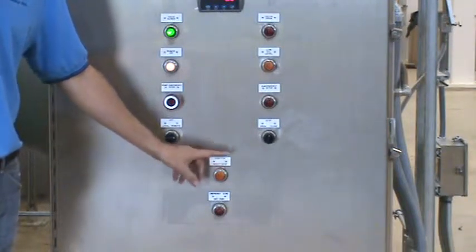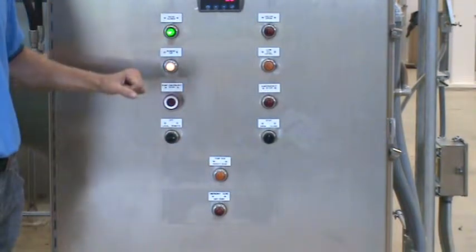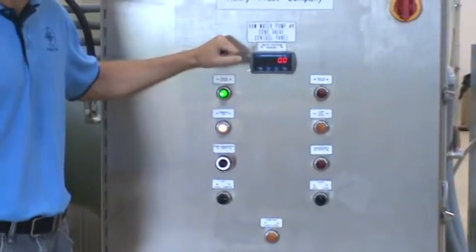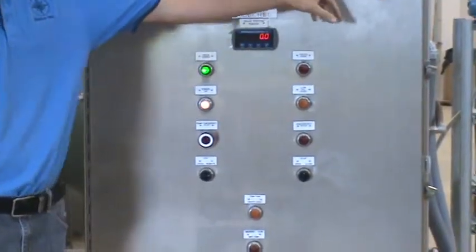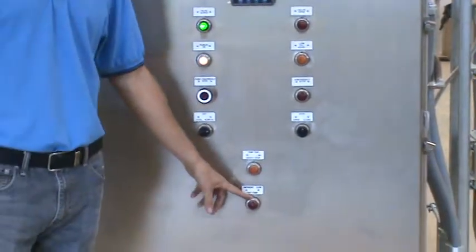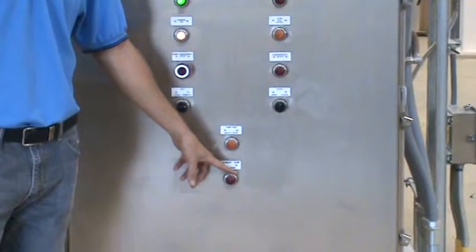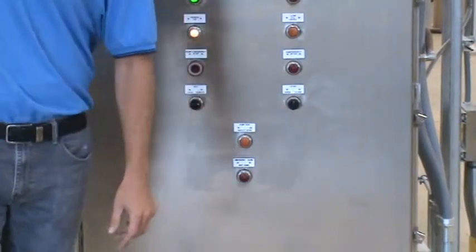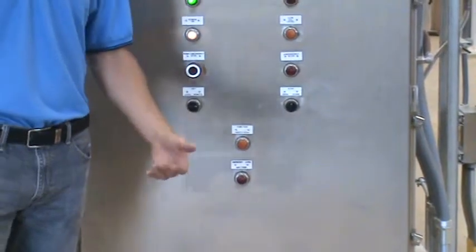There's a safety stop which activates when either the accumulator pump has been running for too long or the power disconnect has been triggered. And then from the soft start controller interface we can send an emergency close signal and shut the cone valve in a fast sequence.